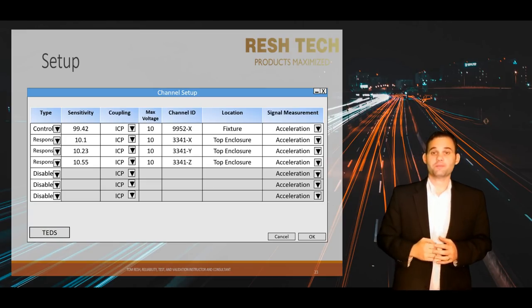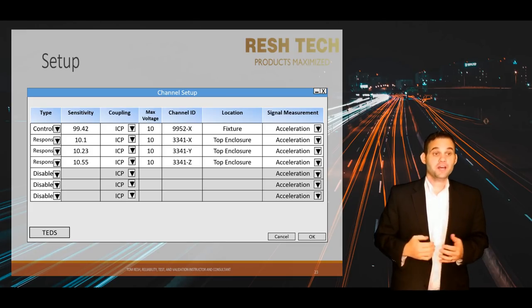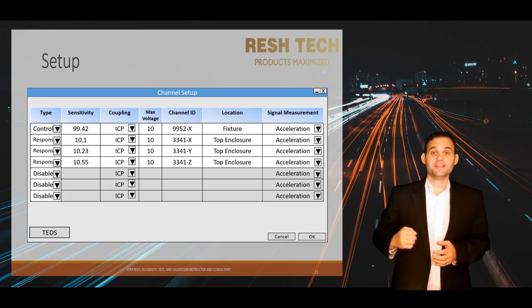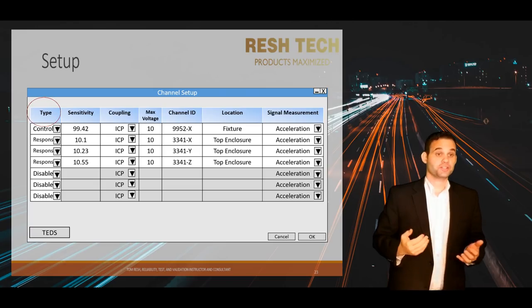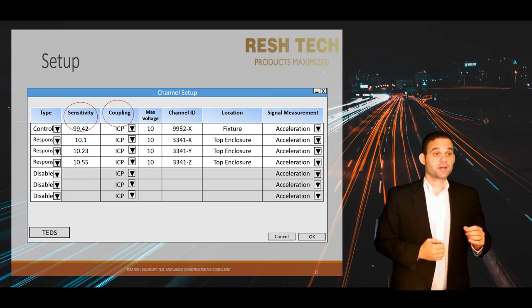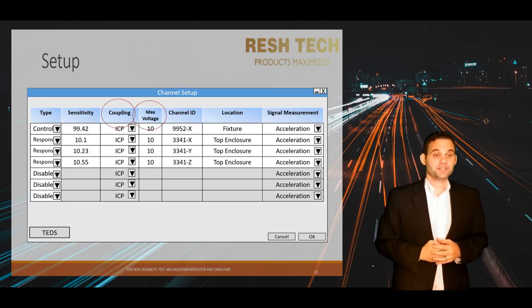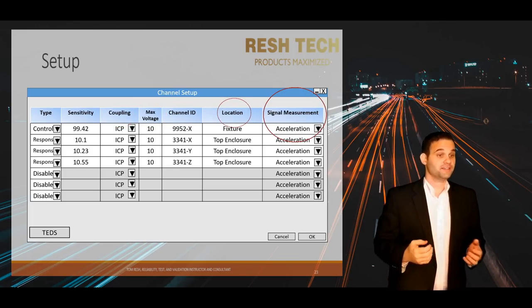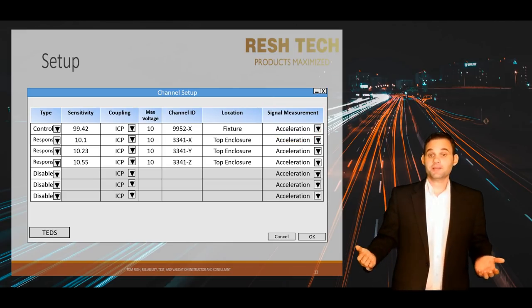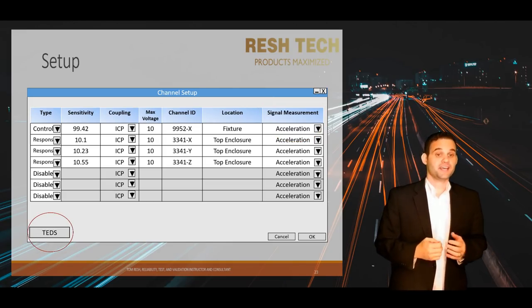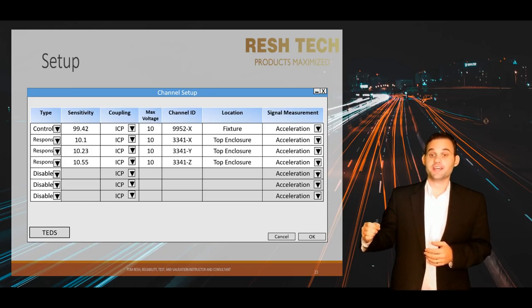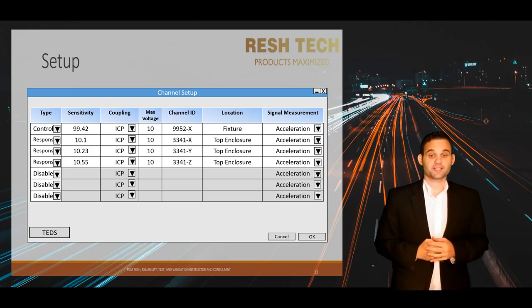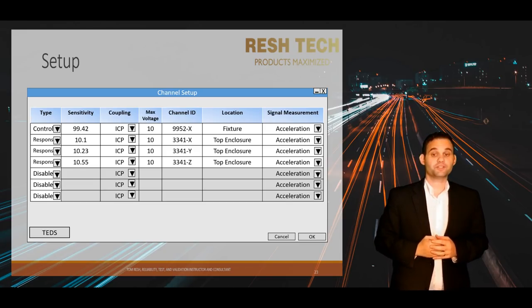Let's take a look at the accelerometer channel setup menu. The key items you will see are channel type, sensitivity, channel coupling, max voltage, channel ID, channel location, and the signal measurement type. Sometimes you will see a TEDS option as well. TEDS stands for Transducer Electronic Data Sheet, and if you have a TEDS accelerometer, you can simply click this option to input most fields based on the stored data within the accelerometer itself.